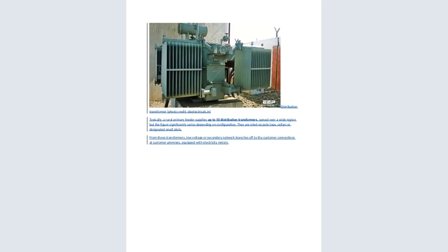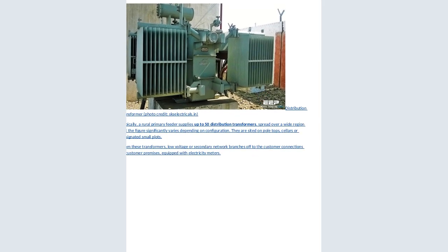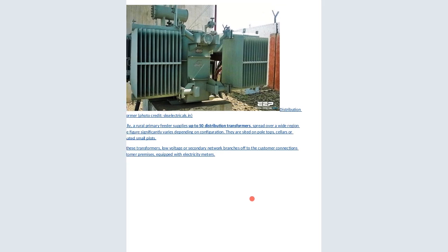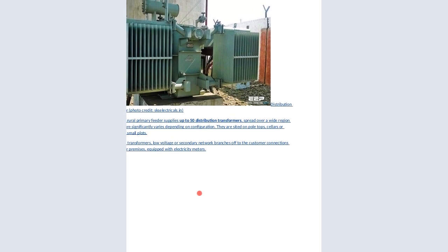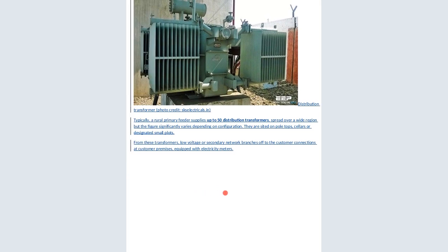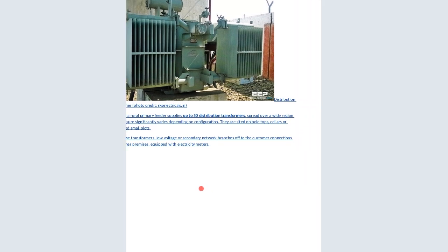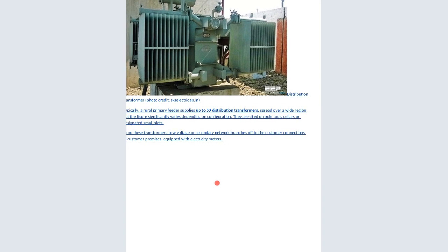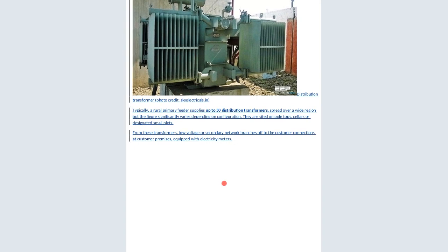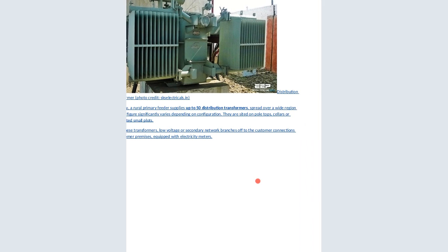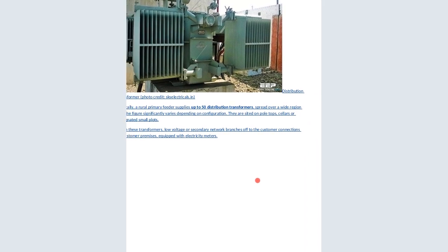So you can see now a transformer is there that is used to step down. That is a picture of a distribution transformer. Typically, a rural primary feeder supplies up to 50 distribution transformers spread over a wide region, but the figure varies significantly depending on the configuration. They are sited on pole tops, cellars, or designated small lots. Now you can see a typical example of that. From these transformers, low voltage or secondary branches go to the customer connections.